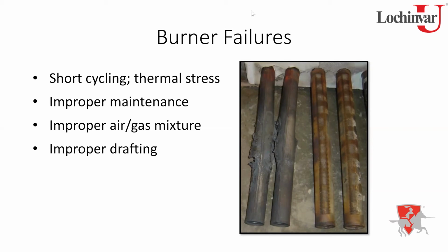I always have a look at the flame inside the combustion chamber. I want to see a nice, strong blue flame that's not pulsating or getting lifted too high off of the burners. If you start to see what looks like a campfire sitting on top of your burners, you have something going on. Again, like Charles said, you've got a blockage, or you've got an improper gas to air mixture entering that combustion chamber, and we're going to have to figure out what's going on. So do keep that in mind.